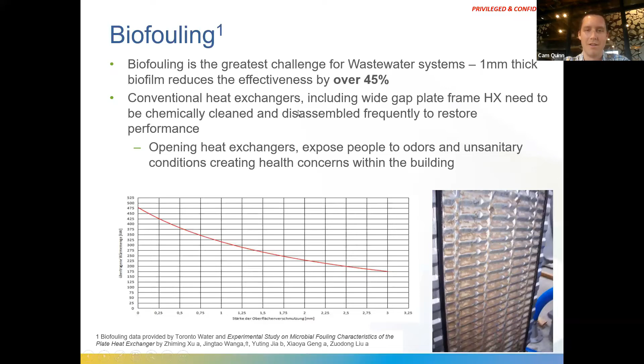A 1 millimeter thick biofilm can reduce the effectiveness of your heat transfer by over 45%. Conventional heat exchangers, including wide gap plate frame heat exchangers, need to be chemically cleaned and disassembled frequently to restore performance. It's not a very desirable job to be opening up and cleaning a heat exchanger that's in sewage service, and on top of that you're exposing people to unsanitary conditions and odors and all of that. So it's not a good thing.